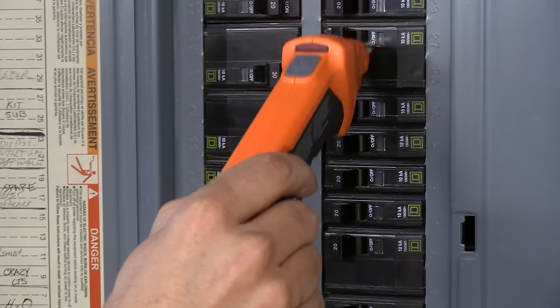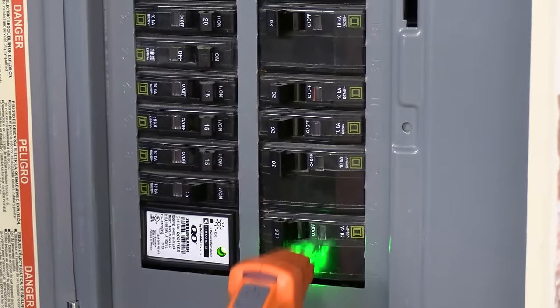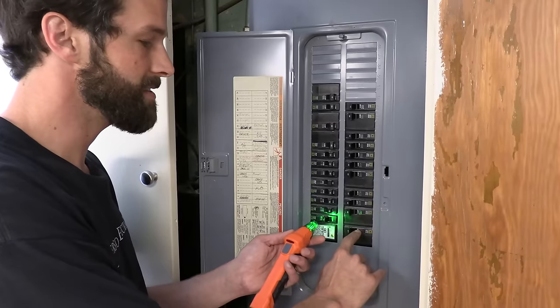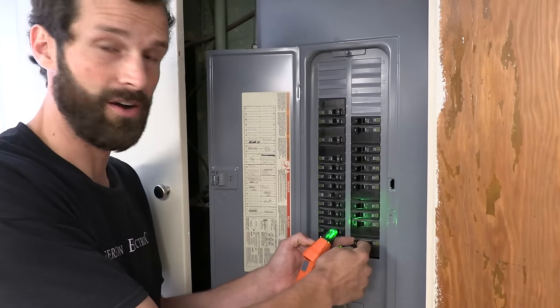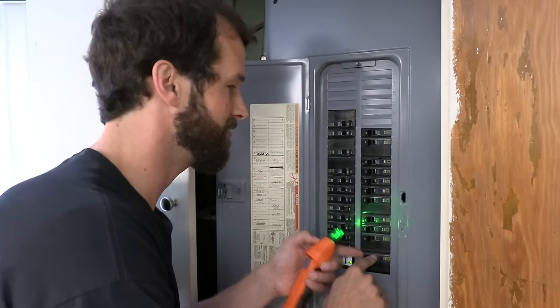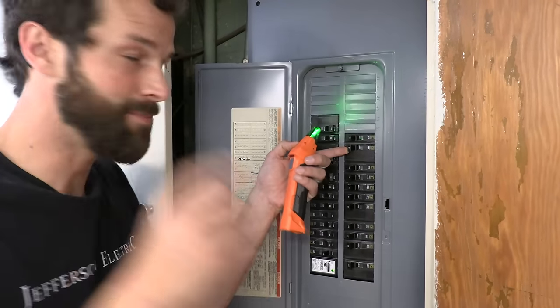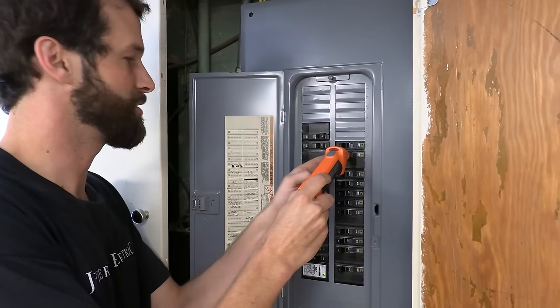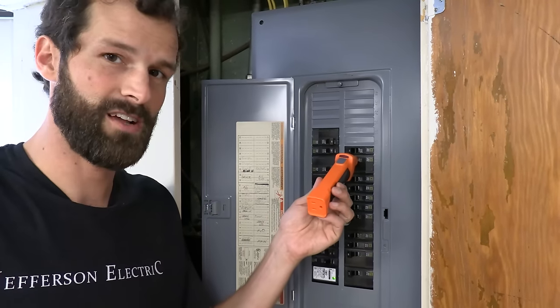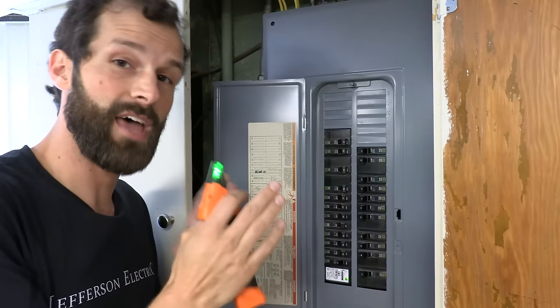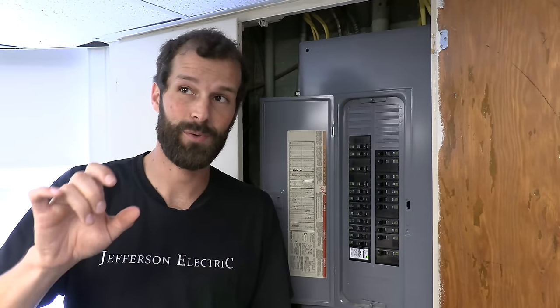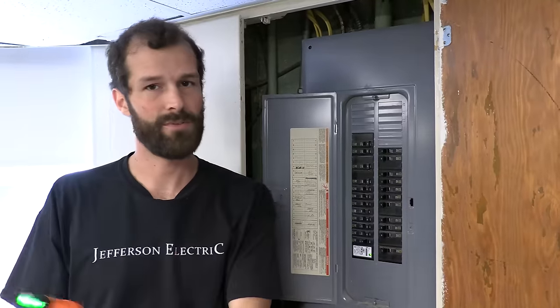I think that's what we're getting. Okay. That's worth talking about. See, it looks like this leg of our panel is feeding that receptacle. But in fact, it's feeding it through this leg of the sub panel upstairs. So check that out. See, that two pole 60, we're pretty sure it's a sub panel just off the kitchen. And that's where we're getting our reading. So that receptacle is going to have a label that lives in the upstairs panel. So time to keep moving.